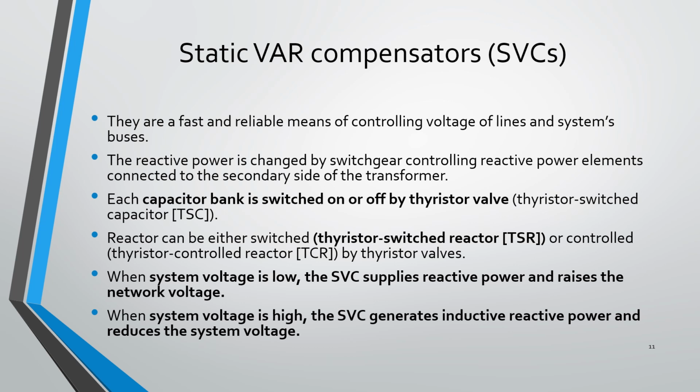Thyristor for that. So reactors can be either thyristor switched reactors or thyristor controlled reactors. That is like TSC, TCR, SVC, like that. These are just the controlling device names. Obviously they are all thyristor controlled, because a thyristor can be controlled by an external signal. So we can control the capacitor or inductor by thyristors, and that's why their names are TSC, thyristor switched capacitor, and TCR, thyristor controlled reactor.